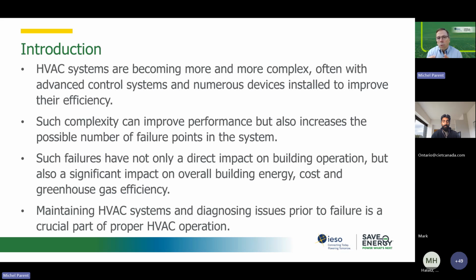So why do we have a session about mechanical issues? Well, HVAC systems are getting more and more complex, especially with the controls that are getting more and more complex. They're getting more efficient and at the same time more complex. In my recommissioning work, usually where I find the most issues is often in the more advanced building. When I deal with a LEED qualified building, it is not uncommon that it's often the building that has the most issues, not because it's not an efficient design, it's just because of the complexity, needs to have a very specific PM program. It has to have specific training for the operator.